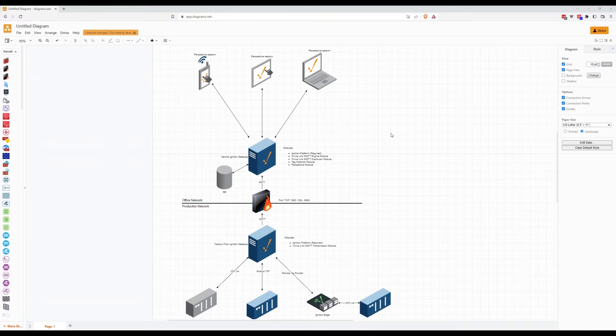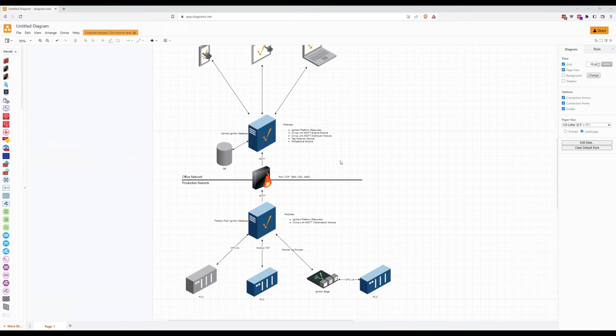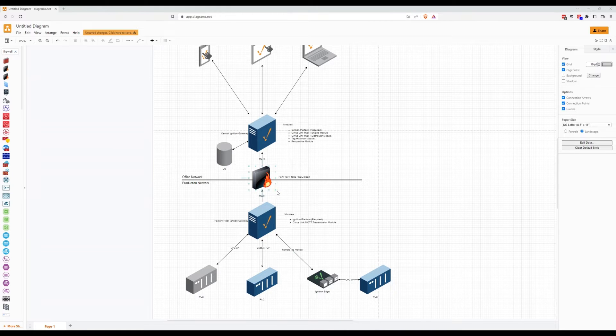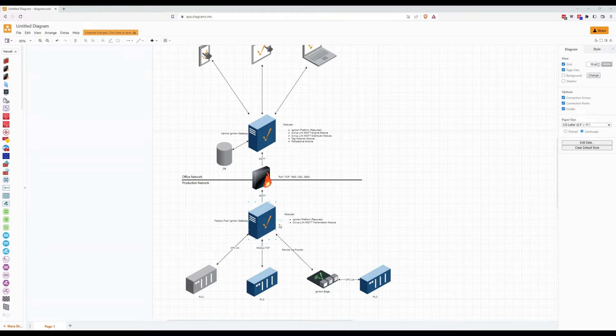The focus today will be mainly on the communication between the factory floor Ignition gateway and the central Ignition gateway, and how we publish tags over MQTT. The reason we have a firewall with arrows pointing only upwards is that when using MQTT, you only need to enable the outbound port — in this case port 1883, or 8883 for SSL encryption. This means the initiation of communication happens from the factory floor gateway to the central gateway; it's not possible to initiate communication in the other direction.